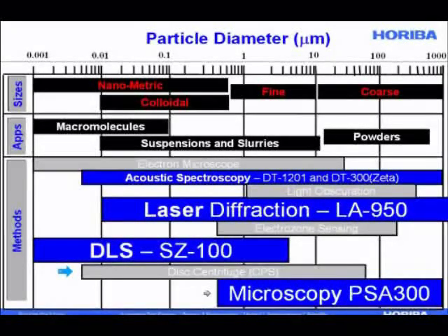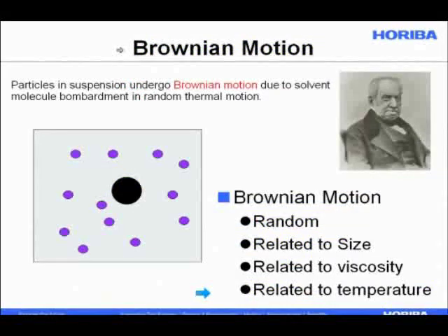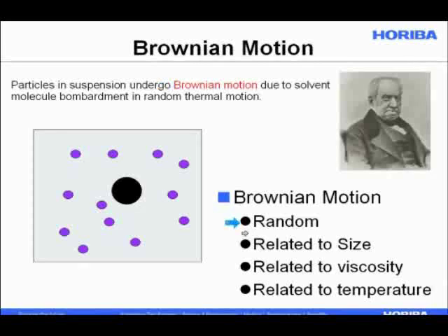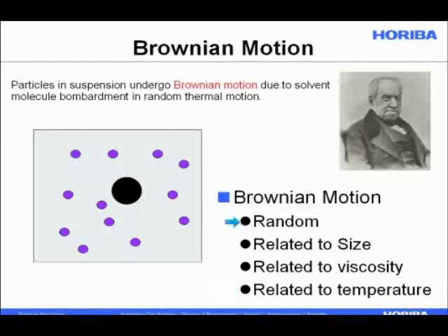When we use dynamic light scattering, we're not looking at the particle directly the way an electron microscope does. Rather, we're probing particle motion. Particles in suspension undergo Brownian motion due to solvent molecule bombardment and random thermal motion — water molecules kick the larger particles and they move around. Brownian motion is random, related to particle size, viscosity, and temperature. Since we can know viscosity and temperature, we interpret the data using a statistical technique to extract particle size.